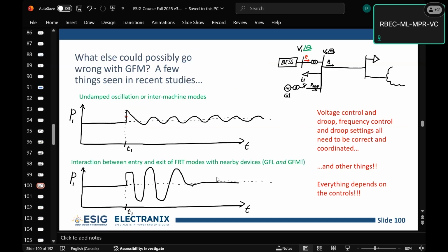And that basically was holding the angle constant artificially and causing the whole island to slip against that one. So it was a pure bug in the system model, but very hard to find. And it caused this massive oscillation across the whole island because of this little source. So just a complete error in the system model. Not that this couldn't happen, but in this case, it was a bit of a red herring.